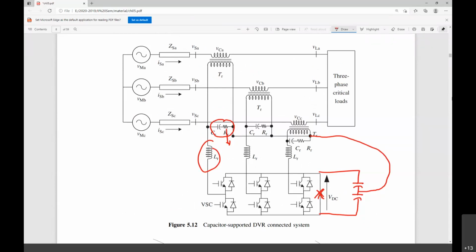Instead of going for the neutral clamp topology, but this neutral clamp topology, there are some issues which are related to the capacitor voltage imbalance. Especially, critically, this is about VDC1, this is going to increase, and the VDC2 is going to decrease.